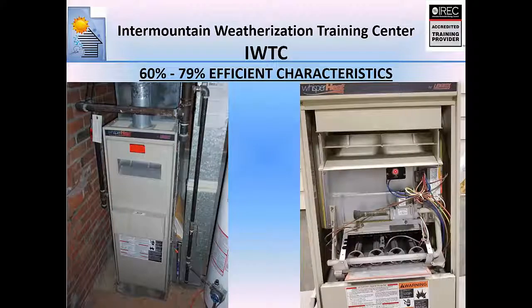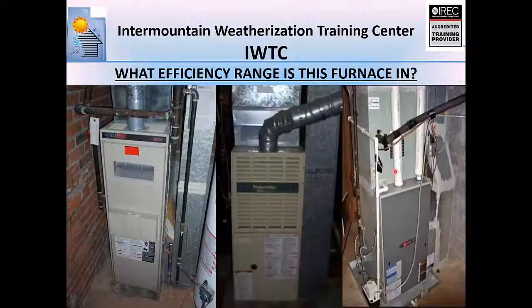Hey, Wade, I got a question on that. Yeah, go ahead. And maybe you plan to cover it, so I apologize. No problem. Which of those requires a worst case draft test? So this one requires worst case draft testing. You'll see why here in a minute. This one does too. This one can backdraft. This one, if it's installed correctly, and we'll talk about the difference in how these can be installed.